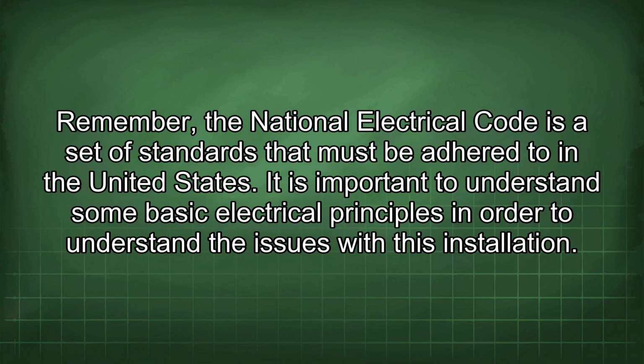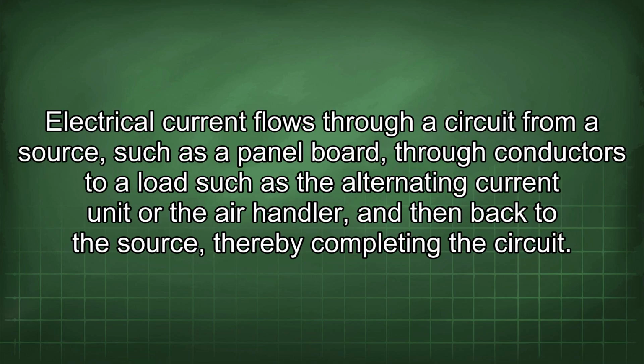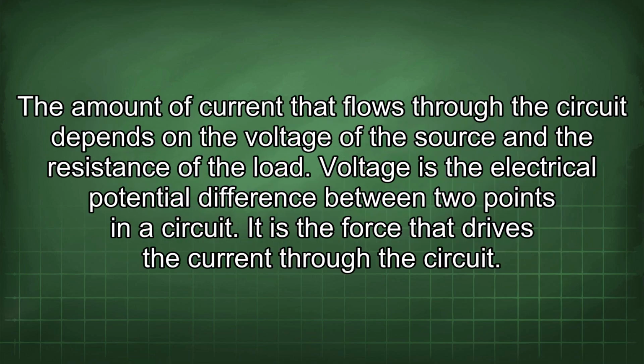It is important to understand some basic electrical principles in order to understand the issues with this installation. Electrical current flows through a circuit from a source, such as a panel board, through conductors to a load such as the alternating current unit or the air handler, and then back to the source, thereby completing the circuit. The amount of current that flows through the circuit depends on the voltage of the source and the resistance of the load. Voltage is the electrical potential difference between 2 points in a circuit. It is the force that drives the current through the circuit.